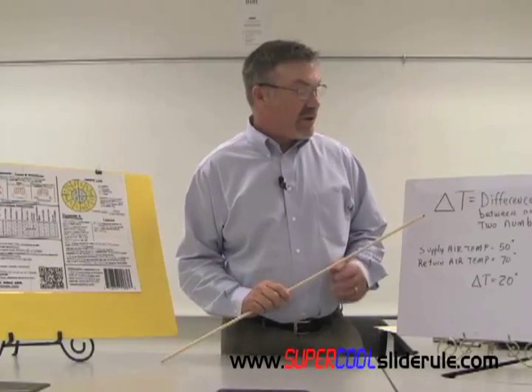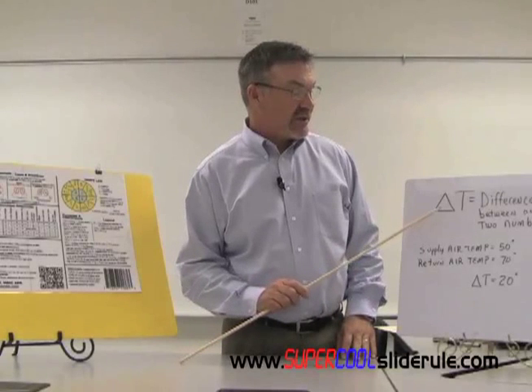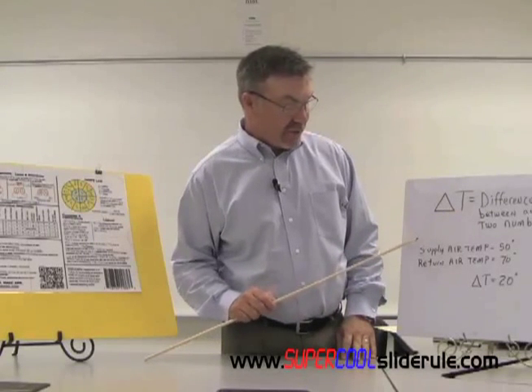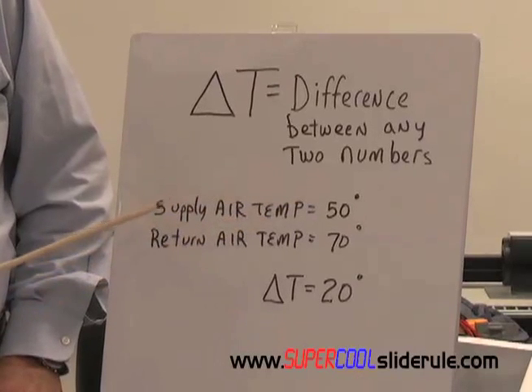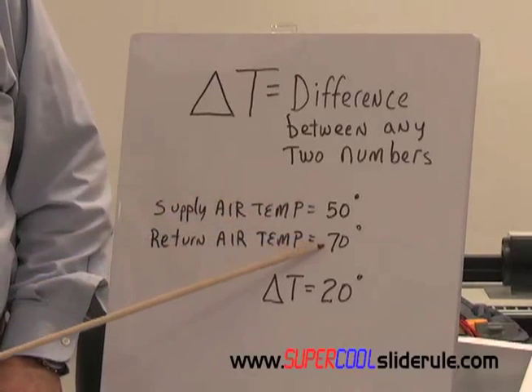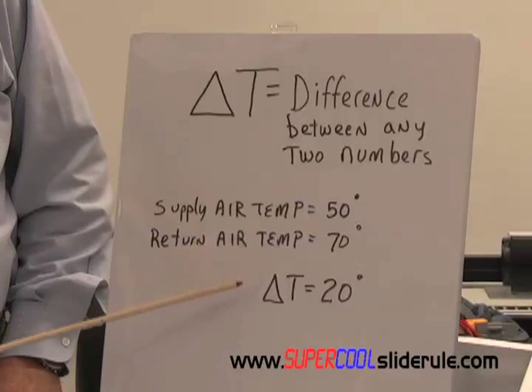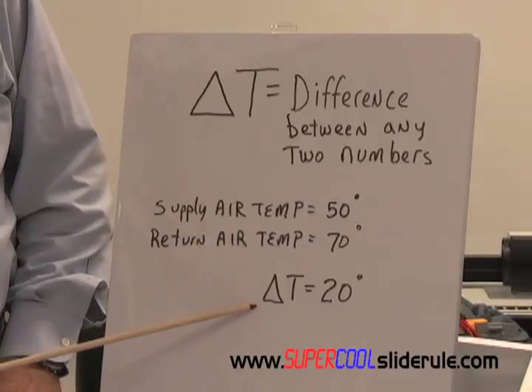So if we want to know what the Delta T is on an air conditioning system, on this one simply we take the supply air temp, which is 50 degrees, the return air temp, which is 70 degrees. The difference between these numbers is 20 degrees and that is your Delta T.